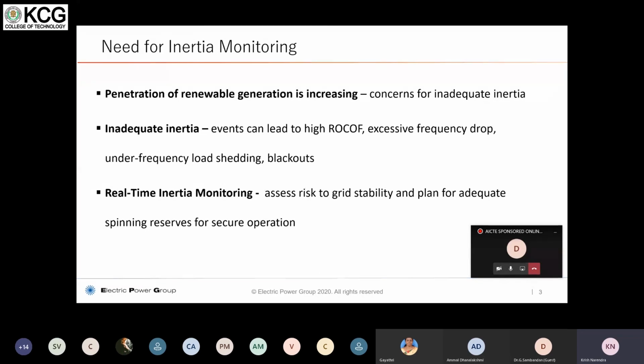What this means is, as I showed you in the first graph of how the dynamic response of the electrical power system happens, you could clearly appreciate that the moment you have lower inertia, it is also associated with a higher rate of change of frequency. If an excessive frequency drop happens, then under-frequency load shedding and under-frequency protection relays will operate, and this may lead to blackouts, because if you are tripping lines which are heavily loaded in a system, it will have huge consequences.